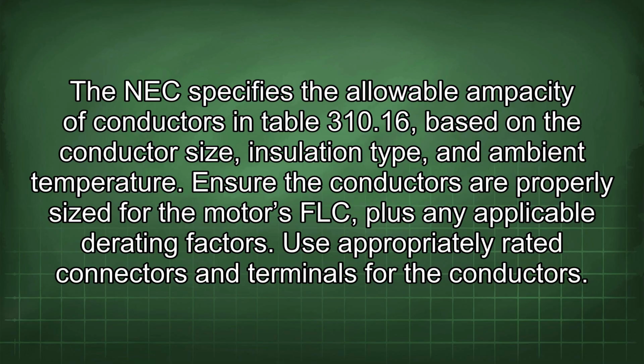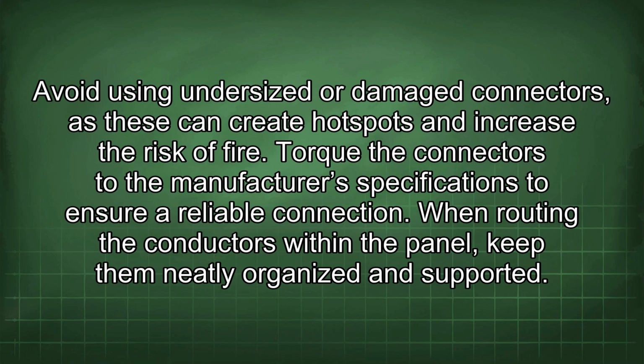The NEC specifies the allowable ampacity of conductors in Table 310.16, based on the conductor size, insulation type, and ambient temperature. Ensure the conductors are properly sized for the motor's FLC plus any applicable derating factors. Use appropriately rated connectors and terminals for the conductors. Avoid using undersized or damaged connectors, as these can create hotspots and increase the risk of fire. Torque the connectors to the manufacturer's specifications to ensure a reliable connection.